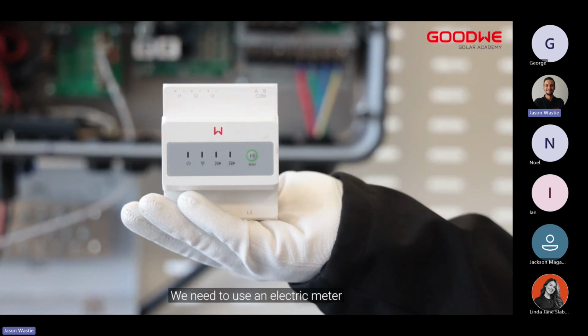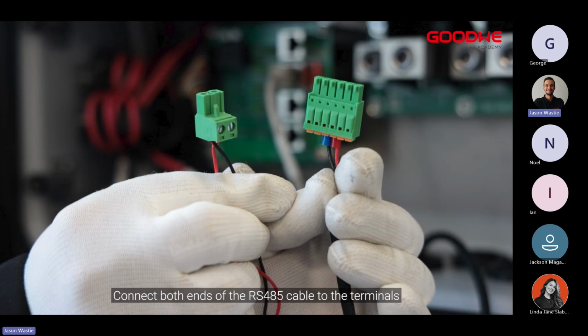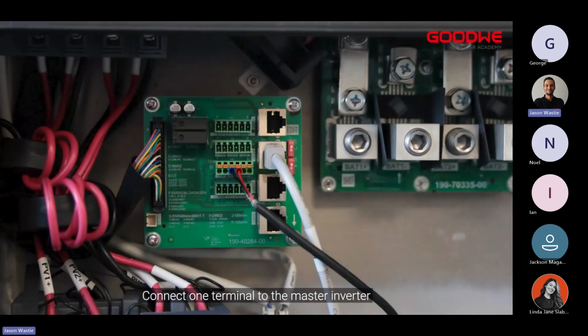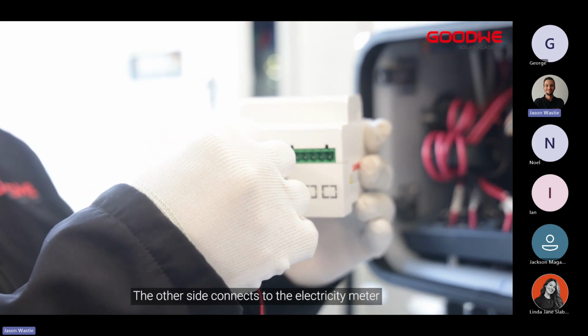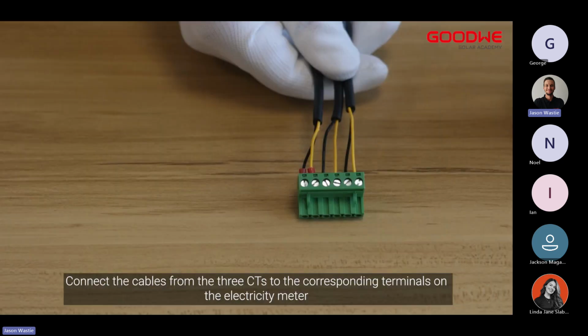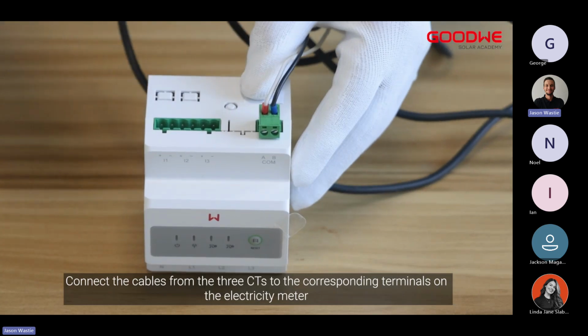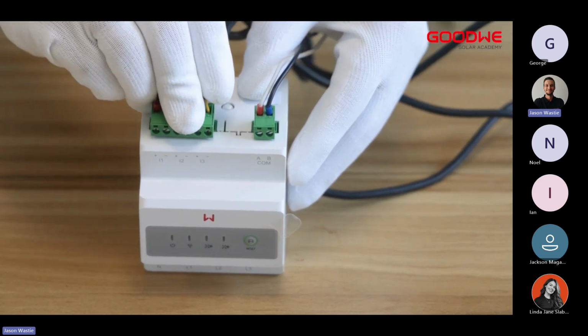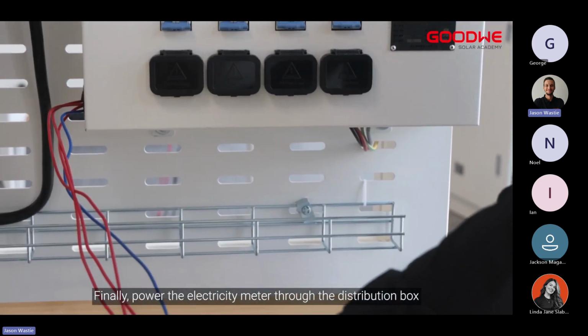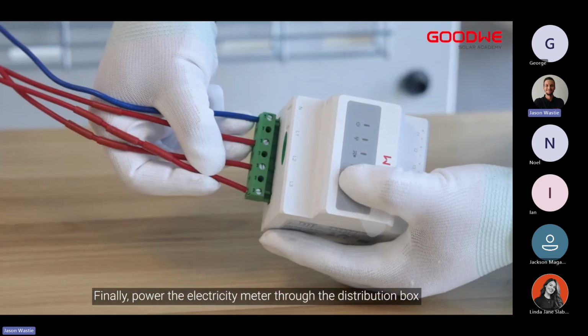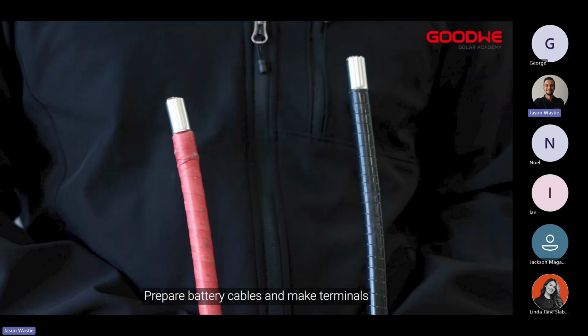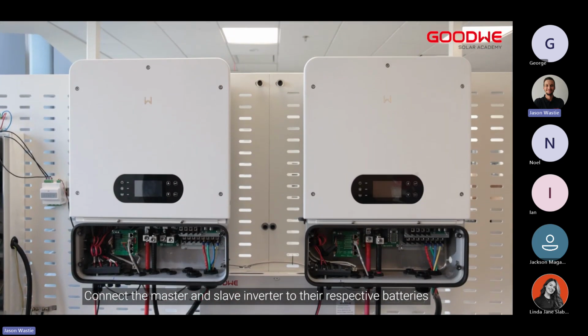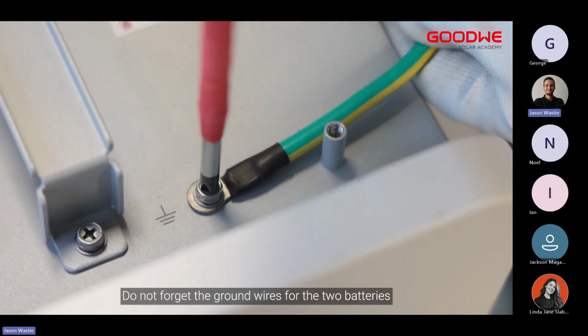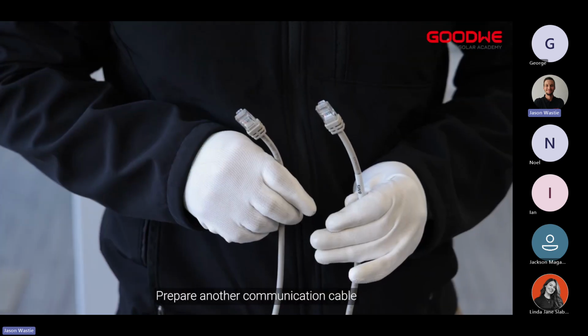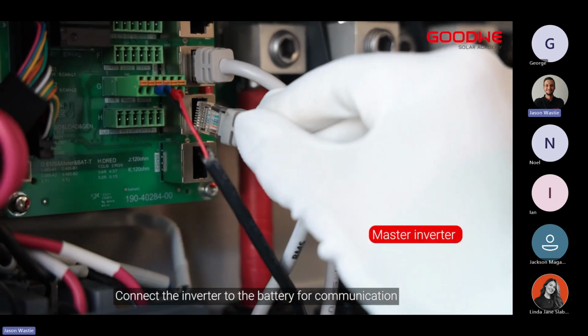We need to use an electric meter. Connect both ends of the RS485 cable to the terminals. Connect one terminal to the master inverter. The other side connects to the electricity meter. Connect the cables from the 3 CTs to the corresponding terminals on the electricity meter. Finally, power the electricity meter through the distribution box. Prepare battery cables and make terminals. Connect the master and slave inverter to their respective batteries. Do not forget the ground wires for the two batteries. Prepare another communication cable. Connect the inverter to the battery for communication.